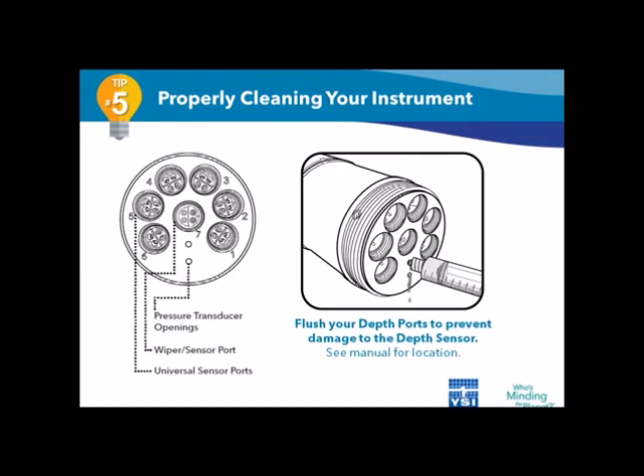Now, all other water quality sensors plug into the sonde, while your depth port or level sensor is built into the sonde body itself. That makes maintaining your depth sensor easy to forget. The depth port is the hole in your sonde where water flows through the instrument into the internal depth sensor.